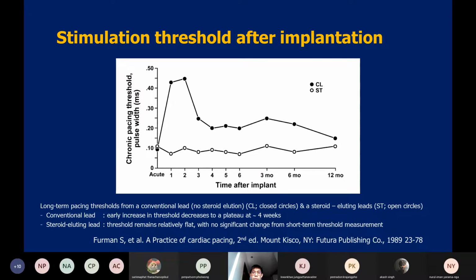This is the graph showing the difference in pulse width and pacing threshold between leads without steroid and steroid eluting leads. The black one, the CL, is the non-steroid eluting or conventional lead, and the white circle is the steroid eluting lead. You can see that the conventional lead has a very high pacing threshold early after implantation, and after that the threshold comes down, but the overall threshold is still higher than the steroid eluting lead. For the steroid eluting lead, the threshold tends to remain relatively low and flat throughout. So if the pacing threshold is lower, the more you can save the energy of the pulse generator, and the longer the patient can use this pacemaker before the battery depletes.